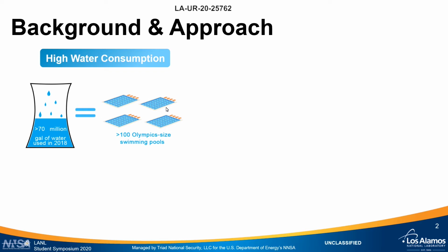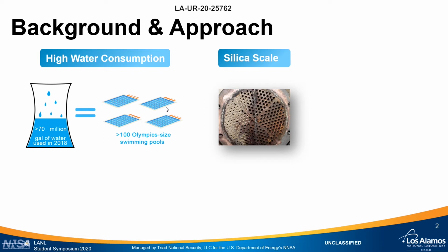The tap water in Los Alamos, New Mexico contains about 90 ppm silica, which is pretty high. Such high concentrations of silica can be problematic for cooling towers, causing silica deposition in heat exchangers, leading to costly maintenance and, in the worst case, reduced efficiency of the cooling systems.